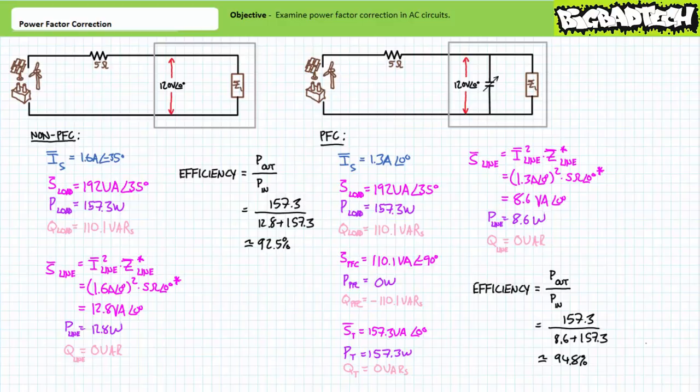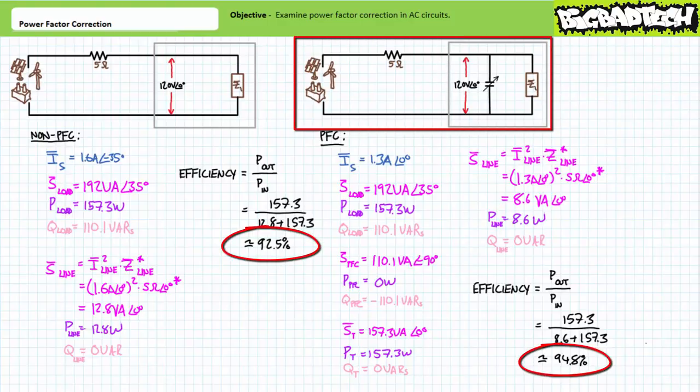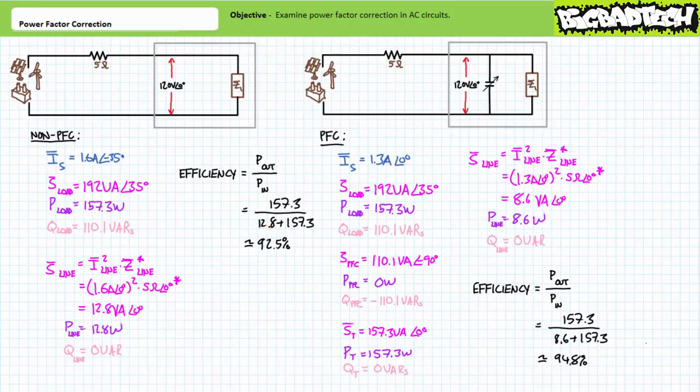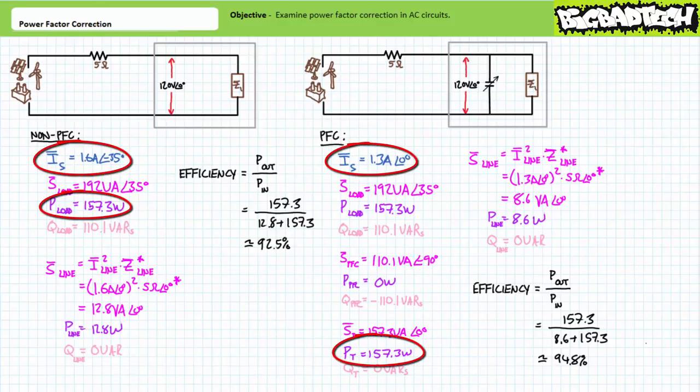Take a moment to consider the implications of this more inclusive perspective. You note by power factor correcting the system inside the room, it increased the efficiency of the larger power distribution system external to the room. Power factor correction essentially frees the generating facility from exchanging reactive power with the system over a distance, given all reactive power requirements are locally juggled back and forth inside the system itself. As a result, source current external to the power factor corrected system needn't be as high. In summary, same real power for less source current yields greater power distribution efficiency. That's why power factor correction is so important.